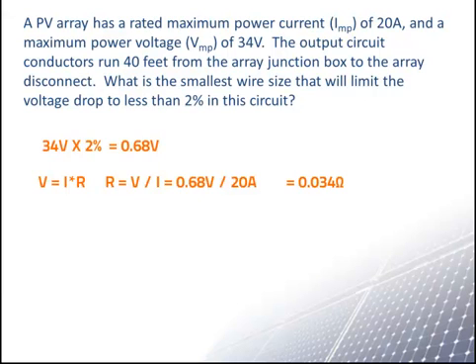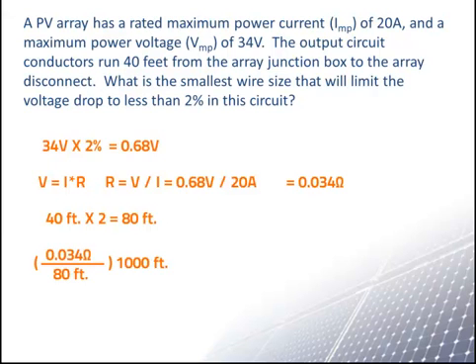Since we have both a positive and a negative wire between the junction box and the disconnect, the travel length of the photovoltaic output circuit conductors is 40 feet times 2, or 80 feet. Therefore, the maximum resistance allowed per 1000 feet of round trip conductor length is 0.034 ohms divided by 80 feet, times 1000 feet, which comes out to be 0.425 ohms per kilofoot.